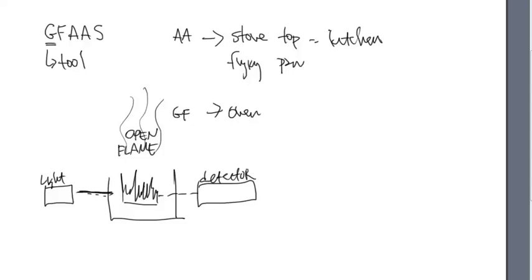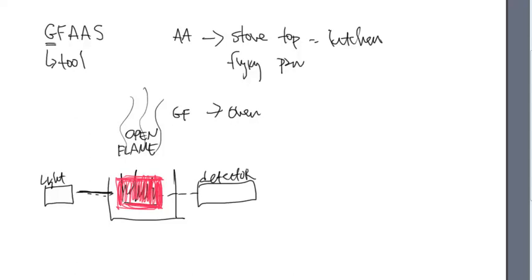Well, I can modify the existing AA instrument, and instead of a frying pan I can decide to bake, and I do it in a closed container. So what happens in a graphite furnace is that here where the burner head is located, there's going to be an attachment, and that attachment is basically a box. I'm going to call it a black box, but this is kind of like an oven. There is no open flame associated with the graphite furnace AA. It is a heated box that's very similar to an oven. This can go to very high temperatures, but more importantly, it is closed.